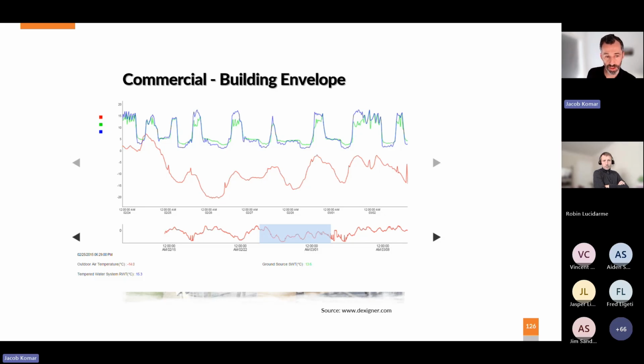At minus 12 degrees Celsius, we are cooling the building. As soon as the sun hit that south wall, you can see we flipped from heating to cooling. This happened the entire week - we're heating at night, cooling during the day, and the building wasn't even fully occupied yet. Now, with the internal gains, this building is basically cooling down to about minus 15, minus 18 degrees Celsius, which is crazy. Commercial buildings are much more cooling dominant.